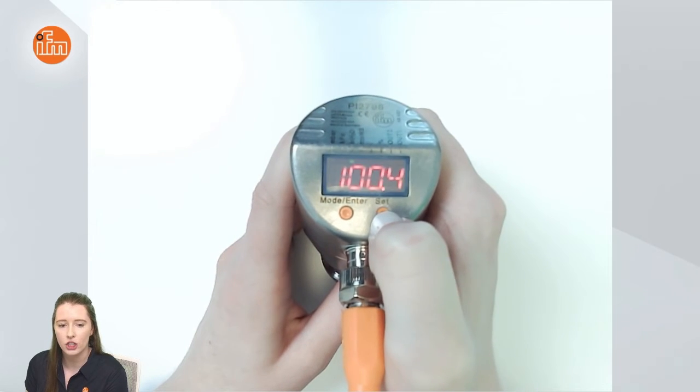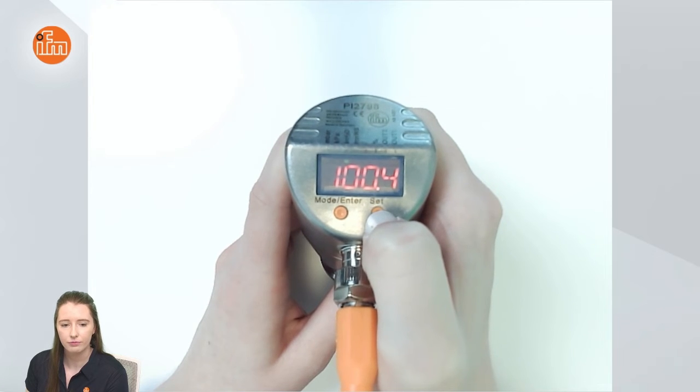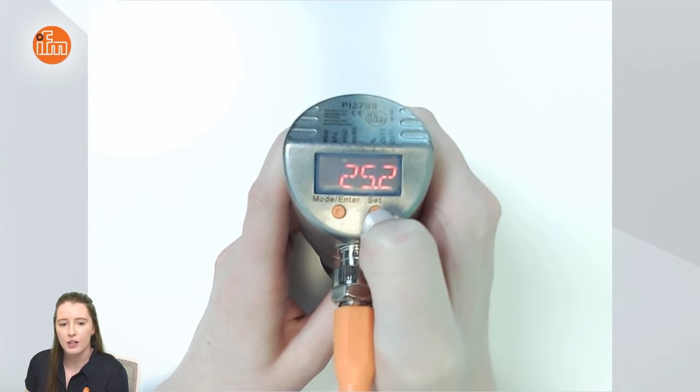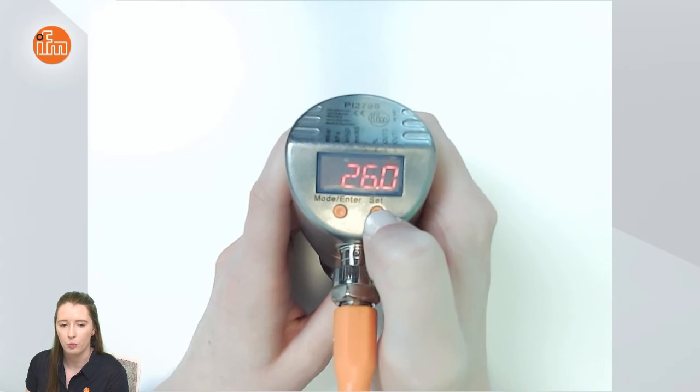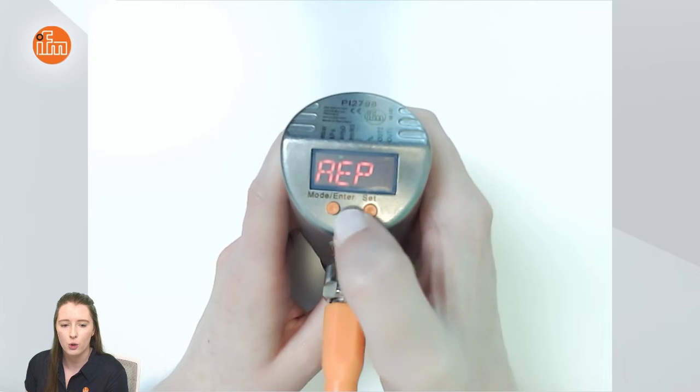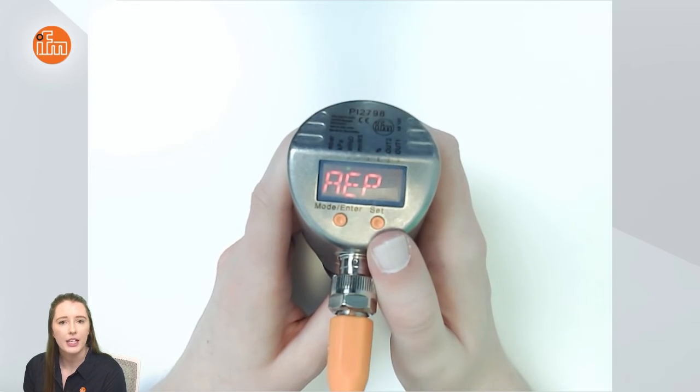It'll begin to flash and then scroll through your options. So for this video I will set it for 26 inches of water column. When you're at the value you want to set it for you'd press mode enter and aep is what is representing the 20 milliamps of your analog output.